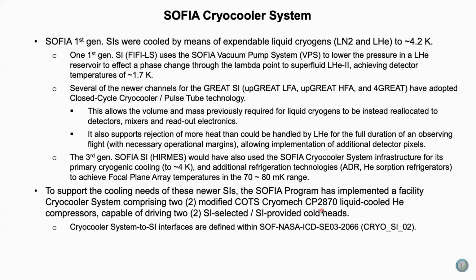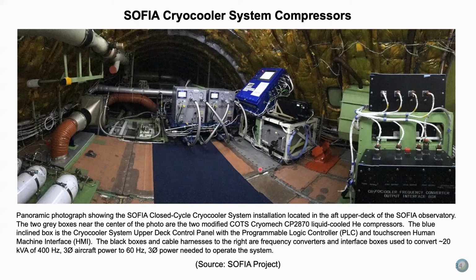So to support the cooling needs of these newer SIs, the SOFIA program implemented a facility cryocooler system comprised of two modified COTS liquid-cooled helium compressors capable of driving two selected SI-provided cold heads. So what that means is that the compressors are provided by SOFIA. The cold heads are provided by whoever is building the SI.